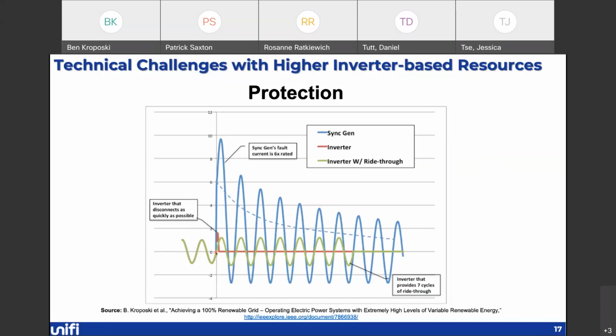You can see here a couple examples. Inverter number 1, this red line, it sees that fault happening and actually disconnects as quickly as possible, and then the fault current goes to 0. Or you can have the inverter programmed to recognize that fault current. It actually is going to produce a little bit more, maybe 1.1 times its rated current, and then it'll ride through here for 7 cycles, and then it'll disconnect. But in either of these cases, they don't look like the blue line, and our protection systems historically, especially overcurrent protection, have been designed to recognize the blue line condition, and it would have a very difficult time discerning these types of outputs when you have low fault contributions from the inverters. So again, just another thing to be aware of.